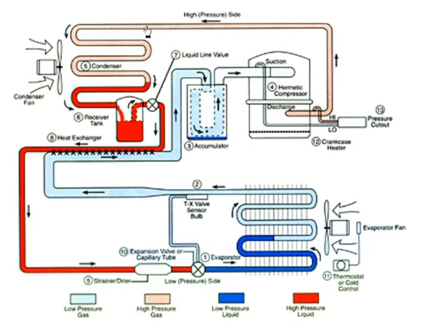So we'll just say you've got a 10 SEER air conditioner. You're probably going to be about, we'll just go 20 degrees hotter. So if it's 80 degrees outside, this line coming out here is going to be about 100 degrees. The amount that this refrigerant cools off really depends on how much air we've got blowing through the coils and how clean the coil is.